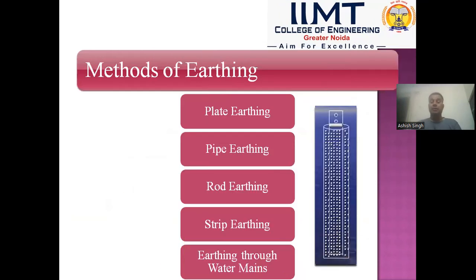And the methods of earthing: there are 5 methods basically used for earthing. First one is plate earthing. In this type of earthing, a plate electrode is buried in the trench, and that is surrounded by alternate layers of charcoal and salt. Second one is pipe earthing.